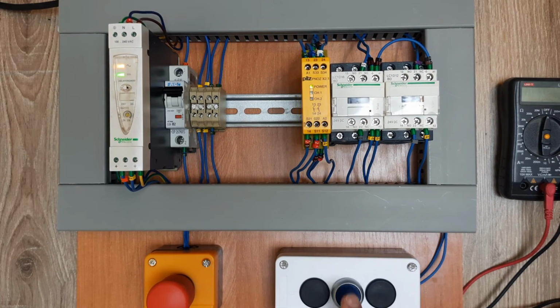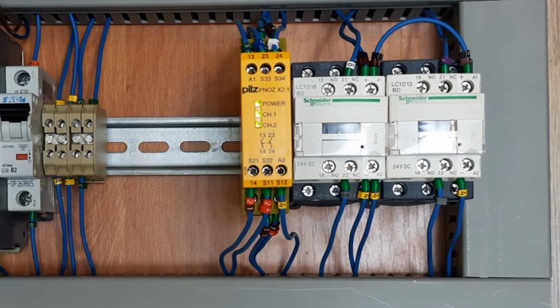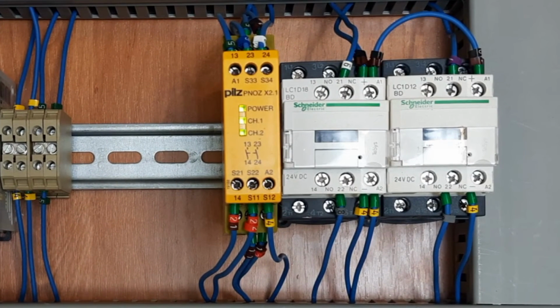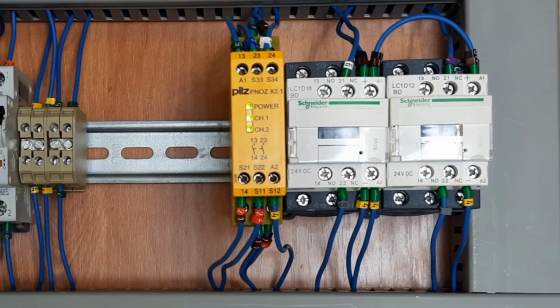To activate safety relay, it is necessary to press start circuit. Then contacts S33 and 34 become closed for a moment. If everything is okay, two LEDs, channel 1 and channel 2, will light up. Safety outputs are closed, energizing external contactors.